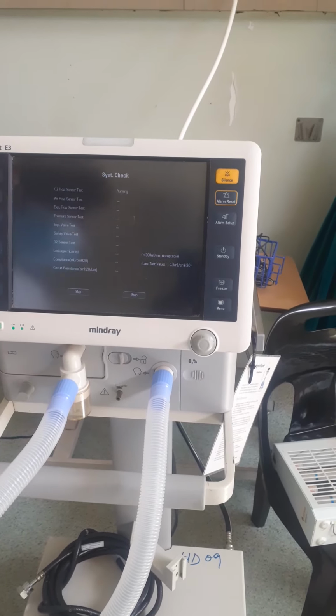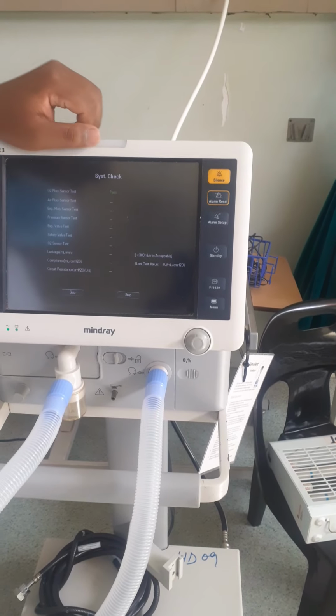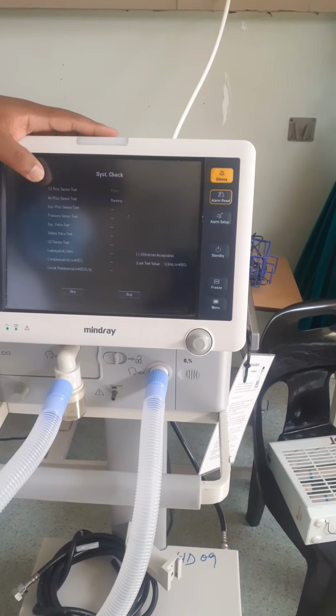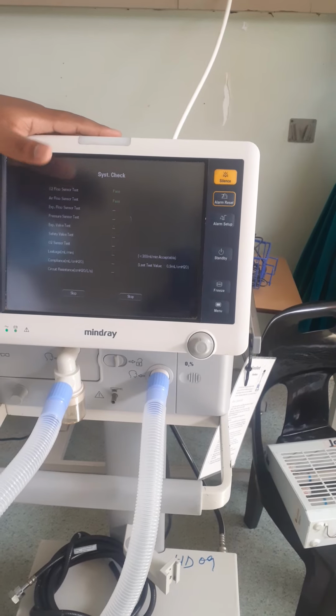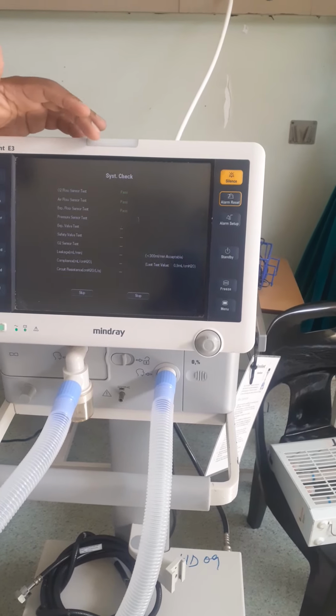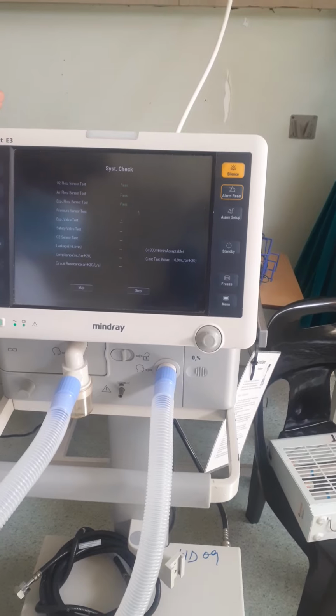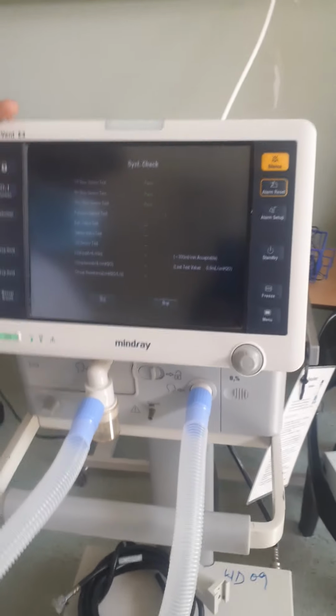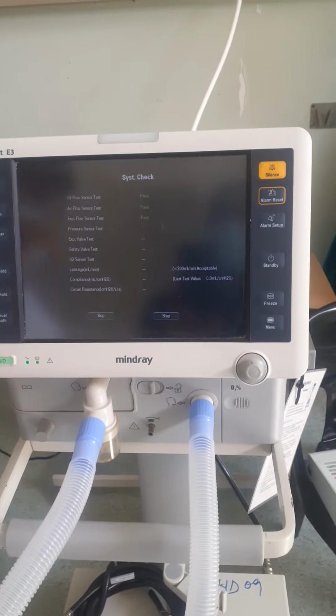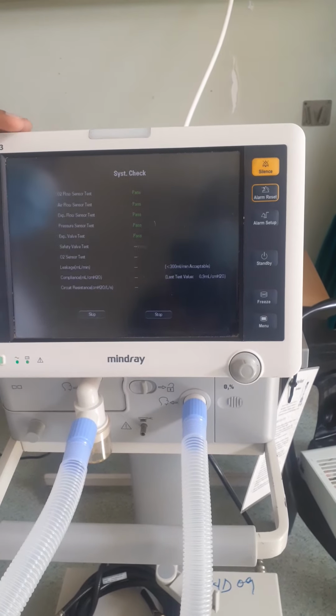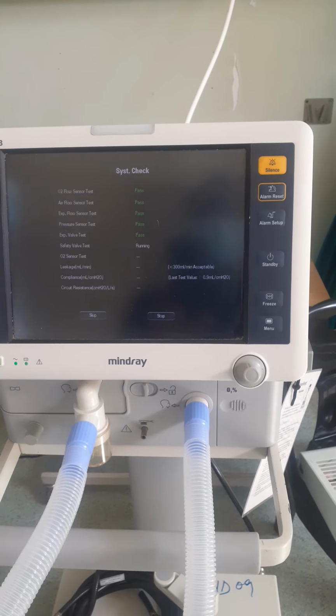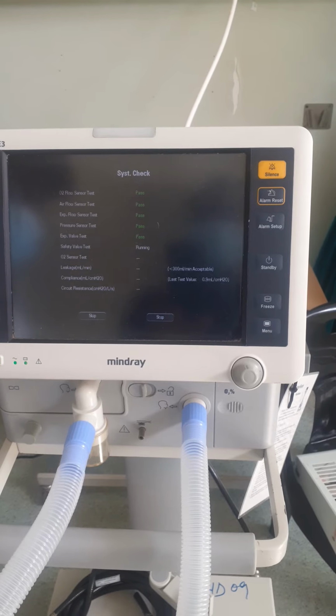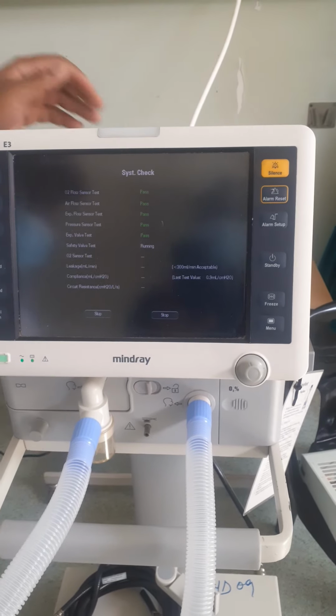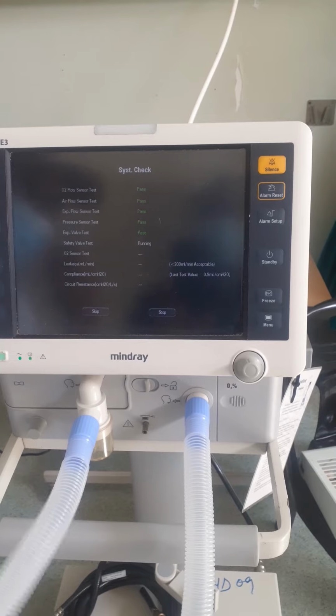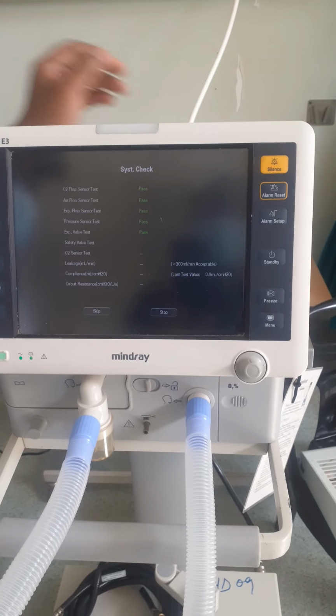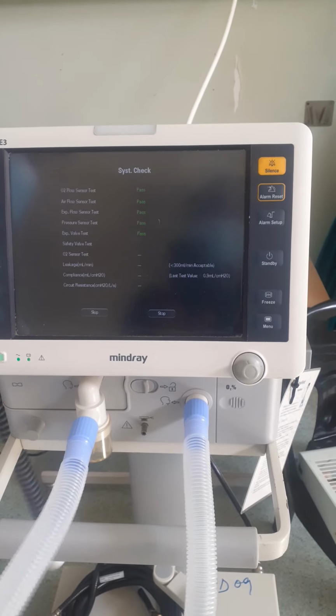Now it's going to check the O2 flow sensor, then the airflow. Now it should pass. Yes, it has passed. Then it's going to run everything. Once it gets to your leakage milliliter, that's when it's going to have a self timer. That timer is going to start from around 80 seconds and count down to 0. From there, that's when you know that this machine can be connected to a patient.